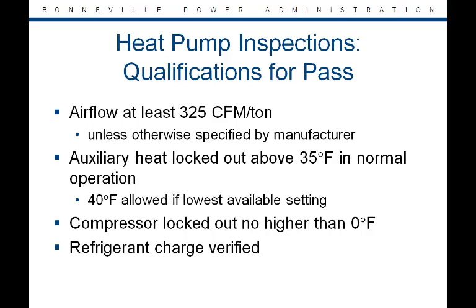PTCS heat pump inspections must confirm airflow, auxiliary heat lockout, compressor lockout, and refrigerant charge. Airflow must be at least 325 CFM per ton, unless otherwise specified by the manufacturer. Auxiliary heat must be locked out at temperatures above 35 degrees Fahrenheit in normal operation. The setting may be as high as 40 degrees for thermostats where that is the lowest possible setting. The compressor should not be locked out at a temperature higher than 0 degrees.